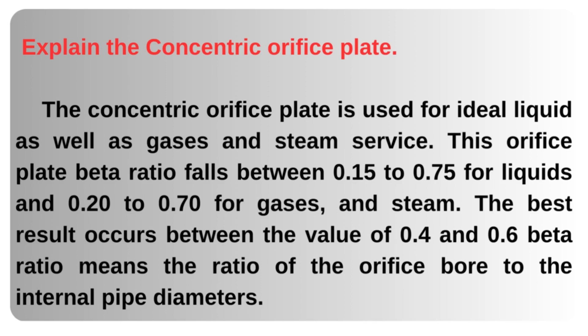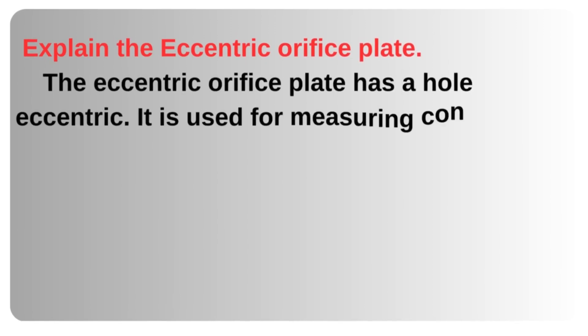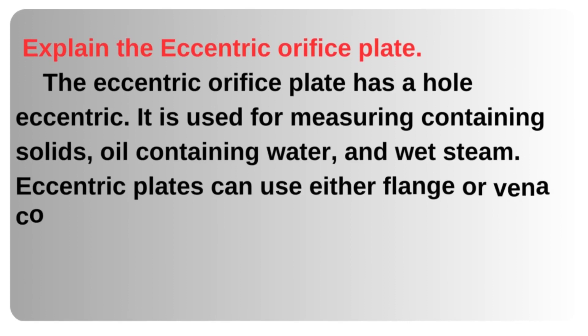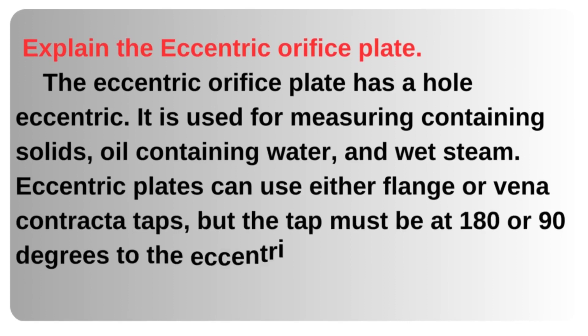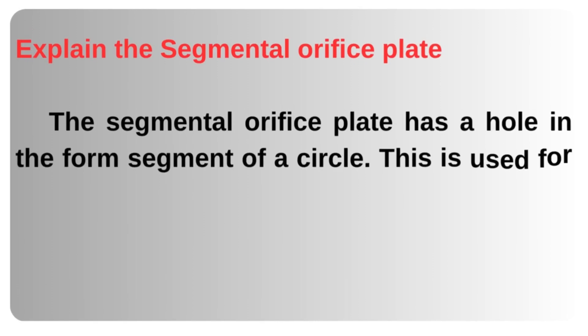Beta ratio means the ratio of the orifice bore to the internal pipe diameter. The eccentric orifice plate has an eccentric hole. It is used for measuring fluids containing solids, oil containing water, and wet steam. Eccentric plates can use either flange or vena contracta taps, but the tap must be at 180 or 90 degrees to the eccentric opening.